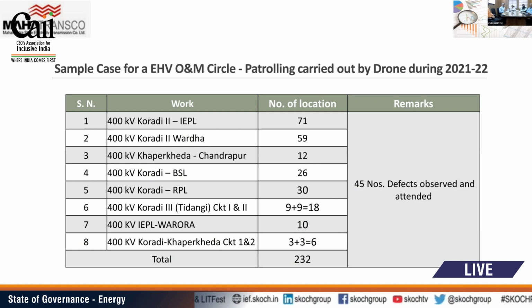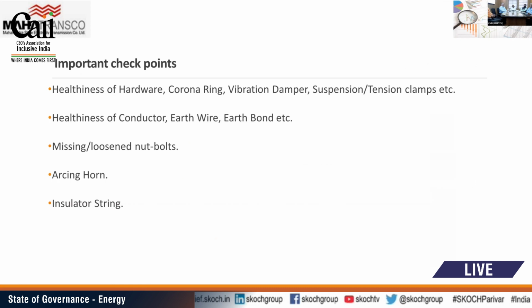I'll brief up about the defects observed. The important checkpoints during inspection are healthiness of hardware, corona ring, vibration damper, suspension and tension clamps, healthiness of conductor and earth wire, earth bond, missing or loosened nut bolts, arcing horn, and insulator strings.